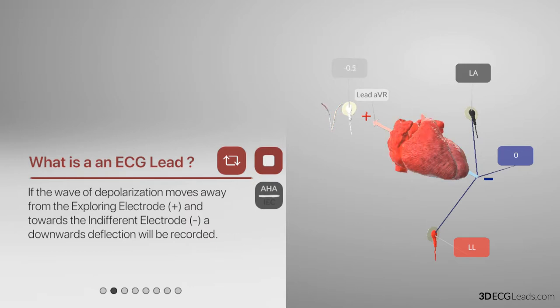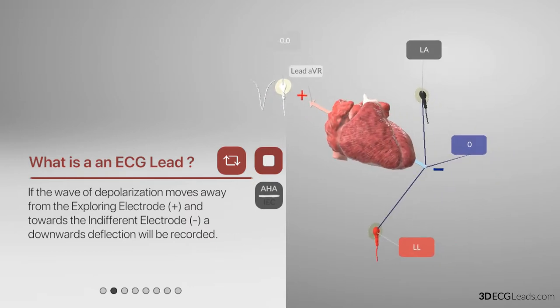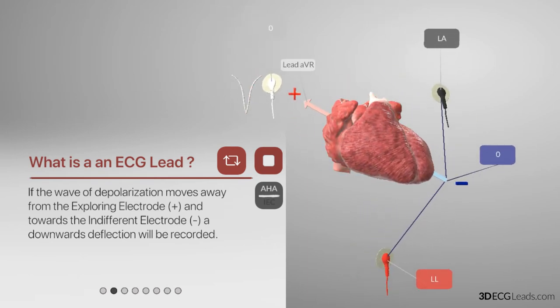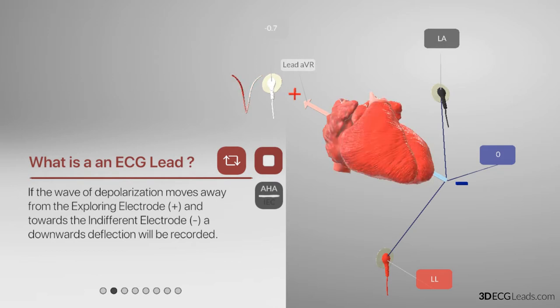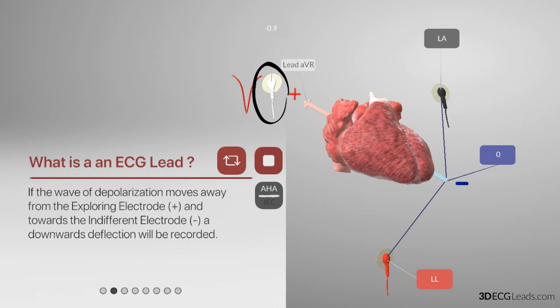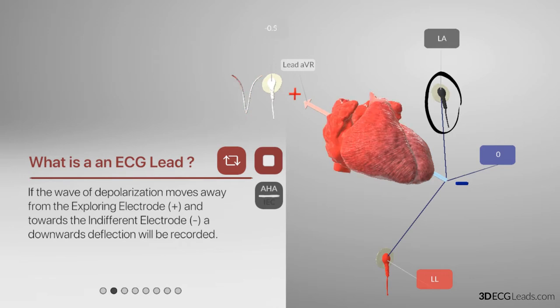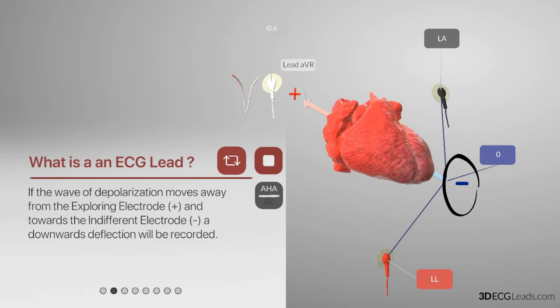Now, what about the negative electrode — what is its role? As we will see, it gives us the orientation of the lead. What you may have spotted is that the negative electrode has changed completely and instead of being one electrode lead, it looks like it is formed by two physical electrode leads. This is how an augmented lead is generated, and the tracing lead here is lead AVR. Tracing lead AVR has the right arm electrode as its positive electrode, and the negative electrode is a virtual electrode resulted from averaging the left arm electrode with the left leg electrode — this is known as Goldberger's central terminal, or simply GCT.